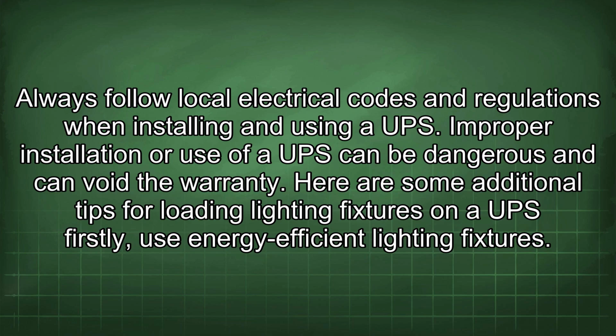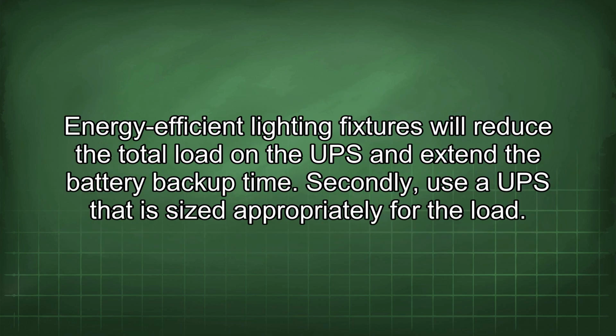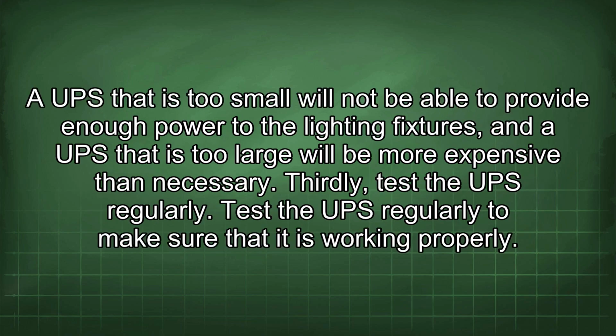Here are some additional tips for loading lighting fixtures on a UPS. Firstly, use energy-efficient lighting fixtures. Energy-efficient lighting fixtures will reduce the total load in the UPS and extend the battery backup time. Secondly, use a UPS that is sized appropriately for the load. A UPS that is too small will not be able to provide enough power to the lighting fixtures, and a UPS that is too large will be more expensive than necessary.